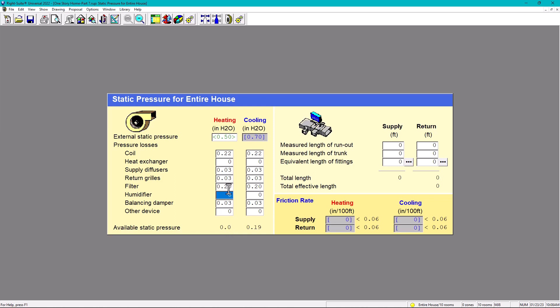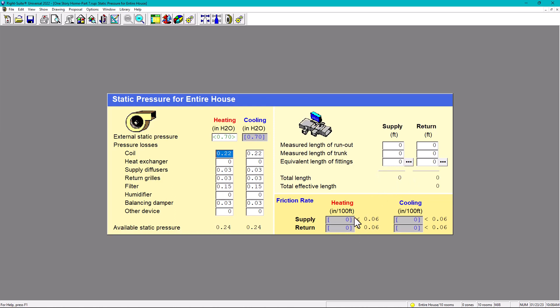We would incur into some issues, or we would have to lower it. So we always check and take into account the worst case scenario. In this case, we're going to put 0.15 for filter and point back to 0.70. Now that we have this, once we draw the duct, this is the total effective length, based on the critical path - the longest path possible. And we're going to calculate the friction rate in here.